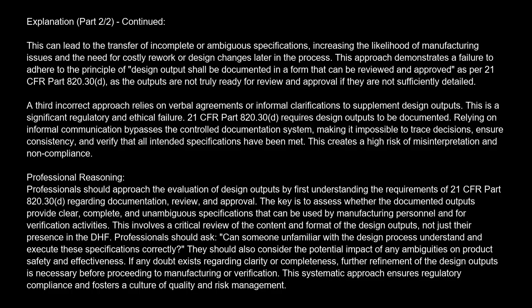Professionals should ask, can someone unfamiliar with the design process understand and execute these specifications correctly? They should also consider the potential impact of any ambiguities on product safety and effectiveness. If any doubt exists regarding clarity or completeness, further refinement of the design outputs is necessary before proceeding to manufacturing or verification. This systematic approach ensures regulatory compliance and fosters a culture of quality and risk management.